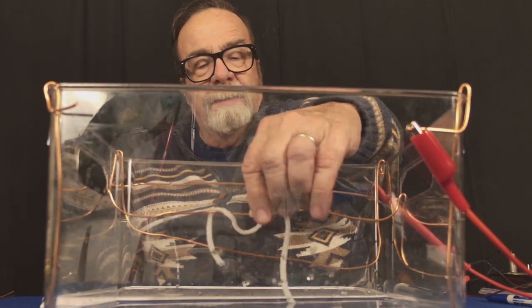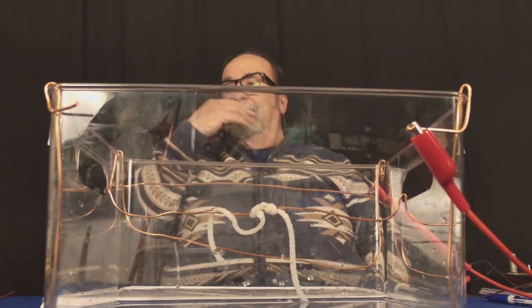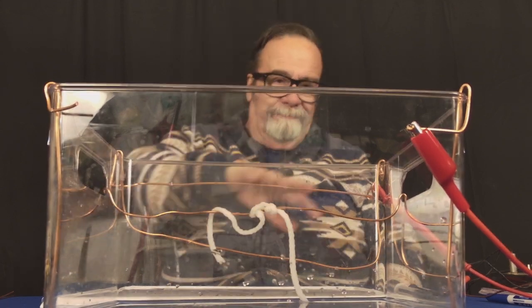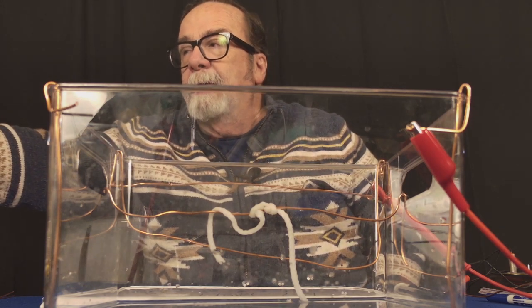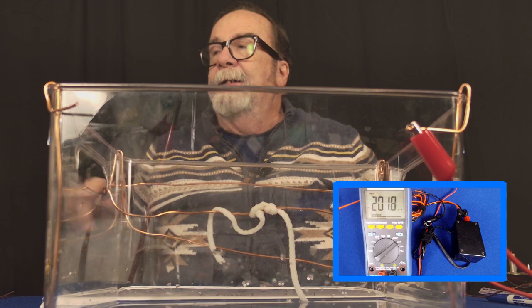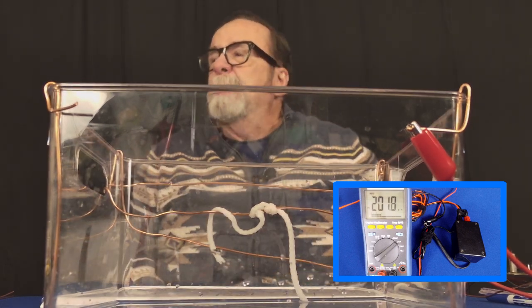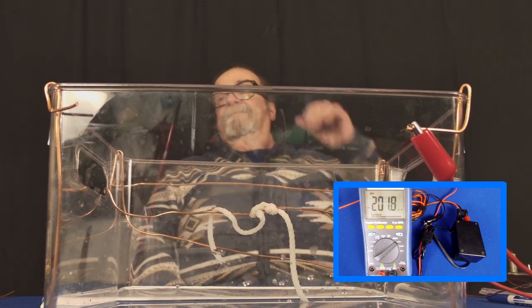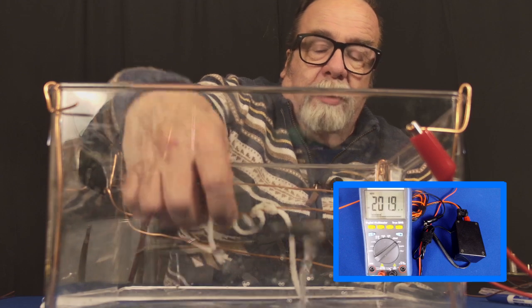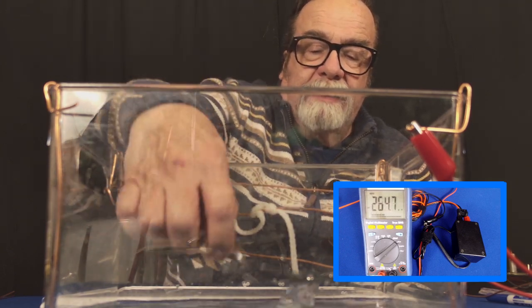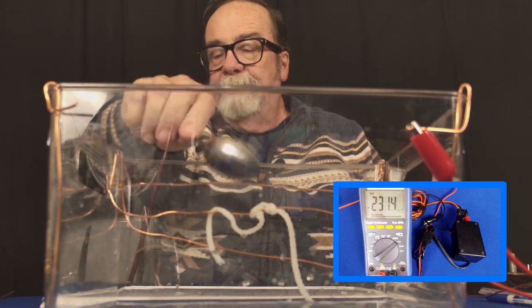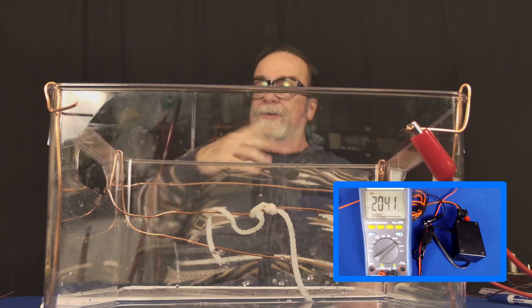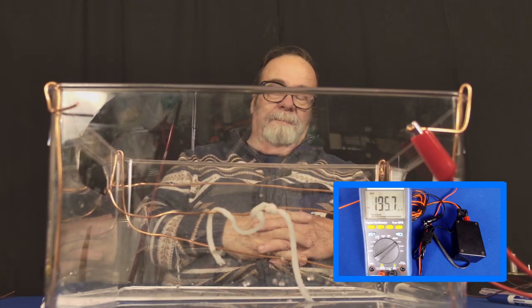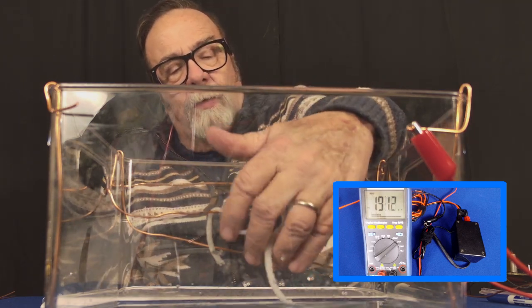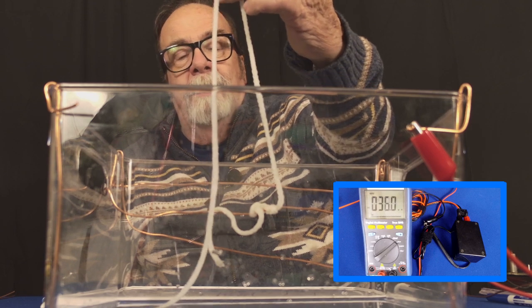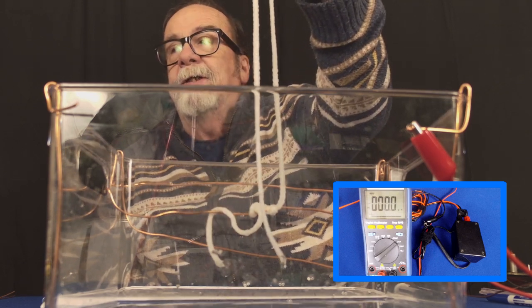It's going in here and you'll notice that there's a rope there and it's sitting in water. So, this is how you use this. With this set up here, I'm going to go ahead and show you the meter while I do this. You'll notice that the meter's reading about 201 microamps. So, as the cable, and think of this rope as a cable, as the cable gets wet inside the conduit, notice how the reading jumps up. Now, you'll notice as it starts to dry out, the current draw goes down. You'll also notice that as I pull it out of the water, I'm going to pull it out slowly. You see how the reading drops and drops and drops until finally it goes away.